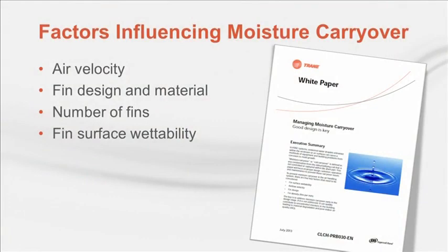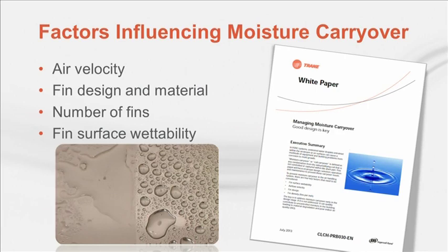This rule has provided satisfactory results broadly but doesn't account for all factors affecting carryover — it's often too conservative, resulting in oversized equipment, or in some cases not conservative enough. The four primary factors contributing to moisture carryover are: air velocity, the design of the fin surface, the material the fins are made of, and fin spacing. Wettability also matters — it describes how easily moisture beads up on the fin surface. A freshly waxed car beads water well, but it's easy for moving air to strip off those droplets, causing carryover. Fin material and corrosion coatings are common features that result in poor fin surface wettability.